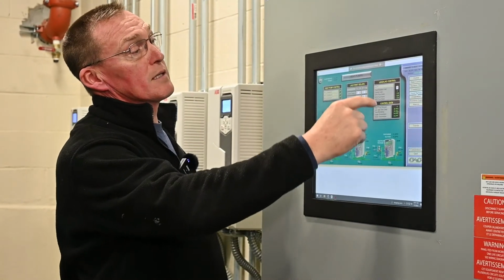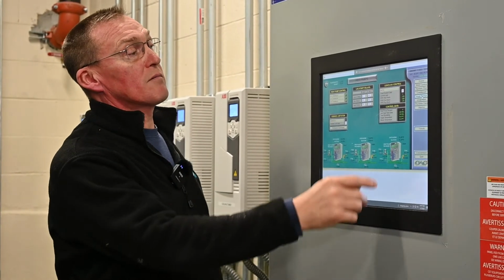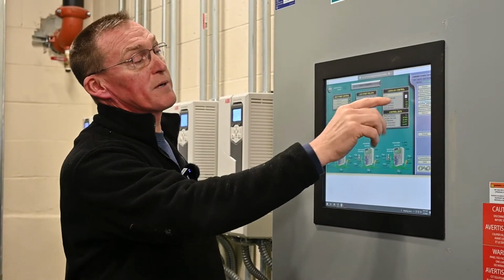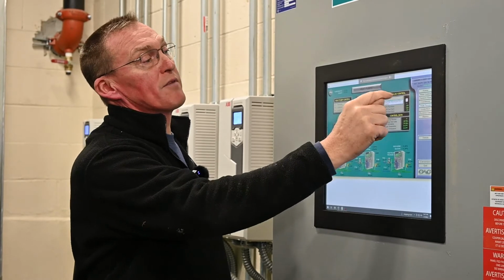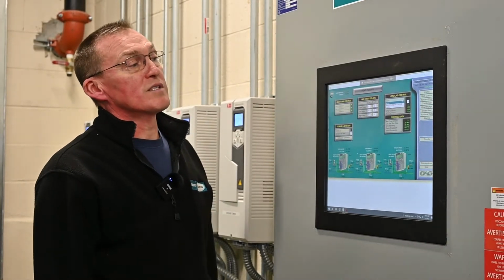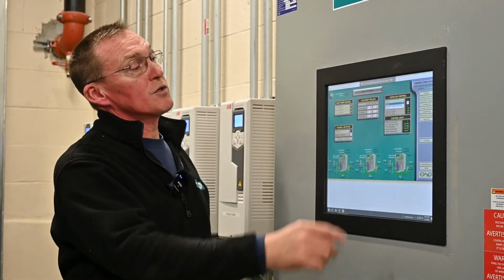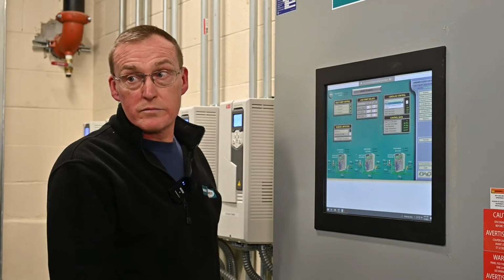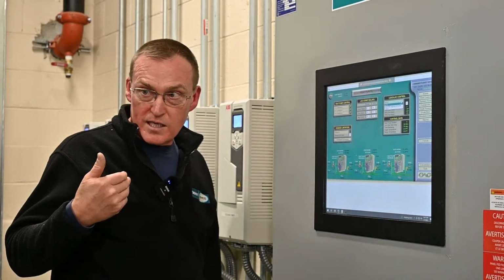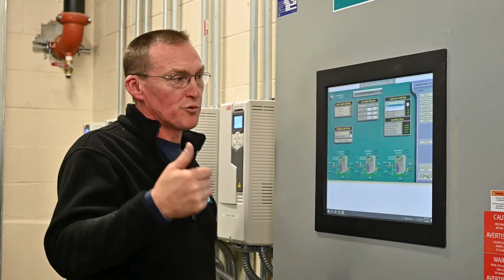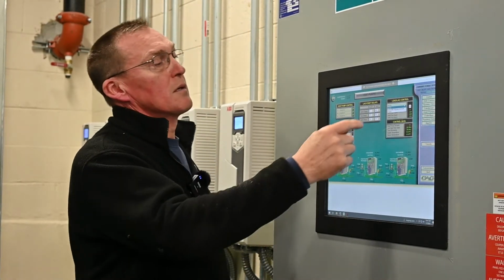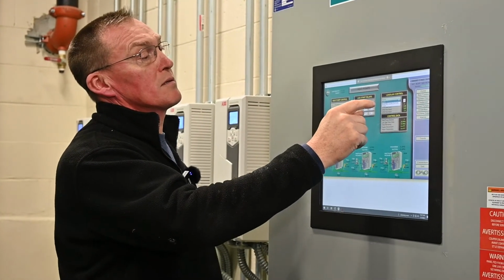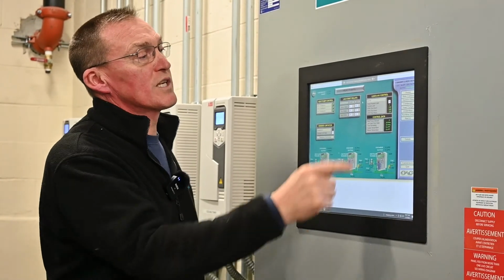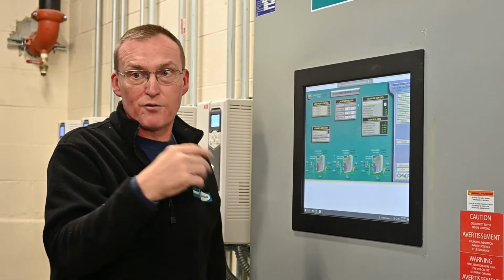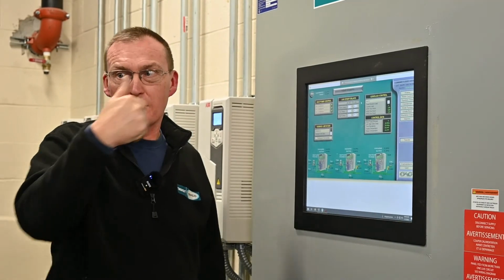Control data, lead lag, fixed rotation. Lead is currently at 3, but we're not running that way. You have the option to run runtime equalization. You can run fixed, or you can run auto. Auto does, as I described, 1, 2, 3, 2, 3, 1, 3, 1, 2. Fixed rotation will run whichever you set it for, whichever is lead. If you set 3 for lead, then it's always going to fire 3, 1, 2.